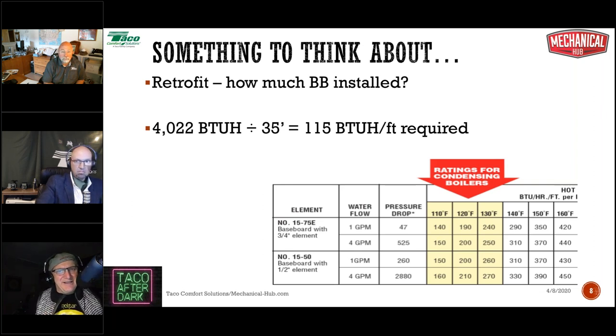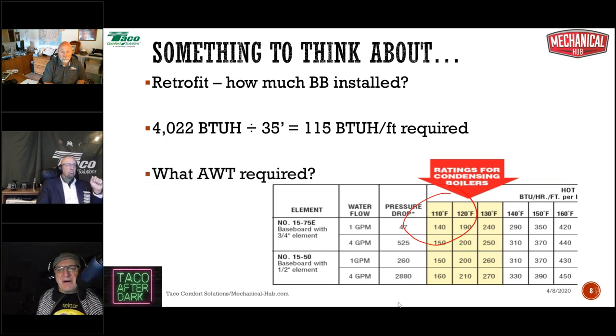That's what I need. So if I take a look at this, what water temperature could I conceivably run? All right, I could conceivably run 120 degrees supply water temperature at a 20 degree delta T, because at 110 degree average water temperature, I'm looking at 140 BTUs per foot and I'm fine. All right, so we've got to think about that.